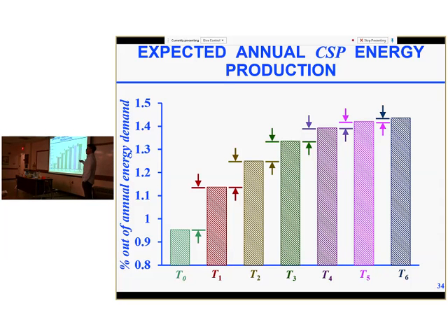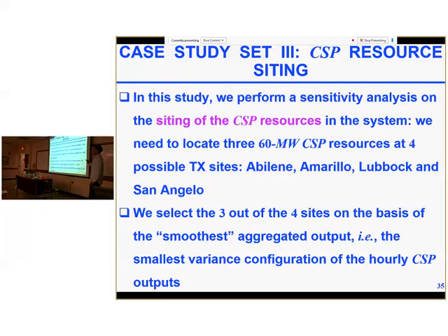It is because the amount of thermal energy that can be received by the CSP is fixed. We cannot increase more. So even though we can increase the storage capability, we do not have enough solar energy to store, so we cannot make full use of the storage. So we can use this approach to do some investment analysis, because it would be a waste to invest in something like 60-hour storage here.